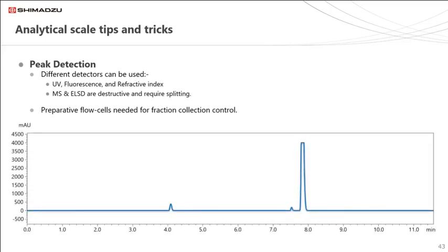This chromatogram shows what happens to the detector signal when a sample is very concentrated. If the peak has an impurity close to the apex, it may not be seen and the peaks will be contaminated. A preparative cell will overcome this.